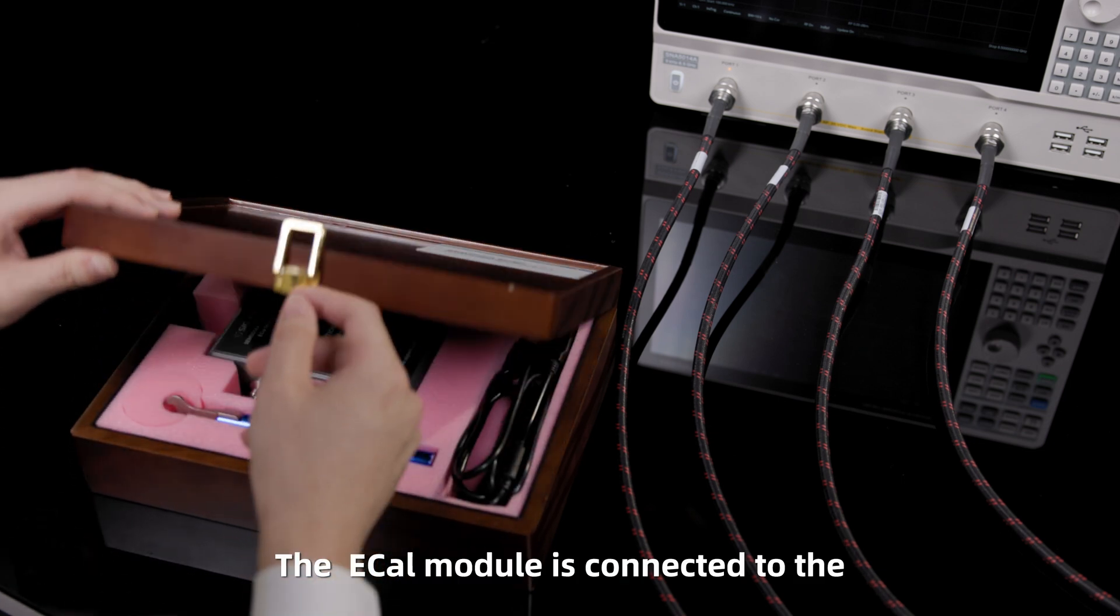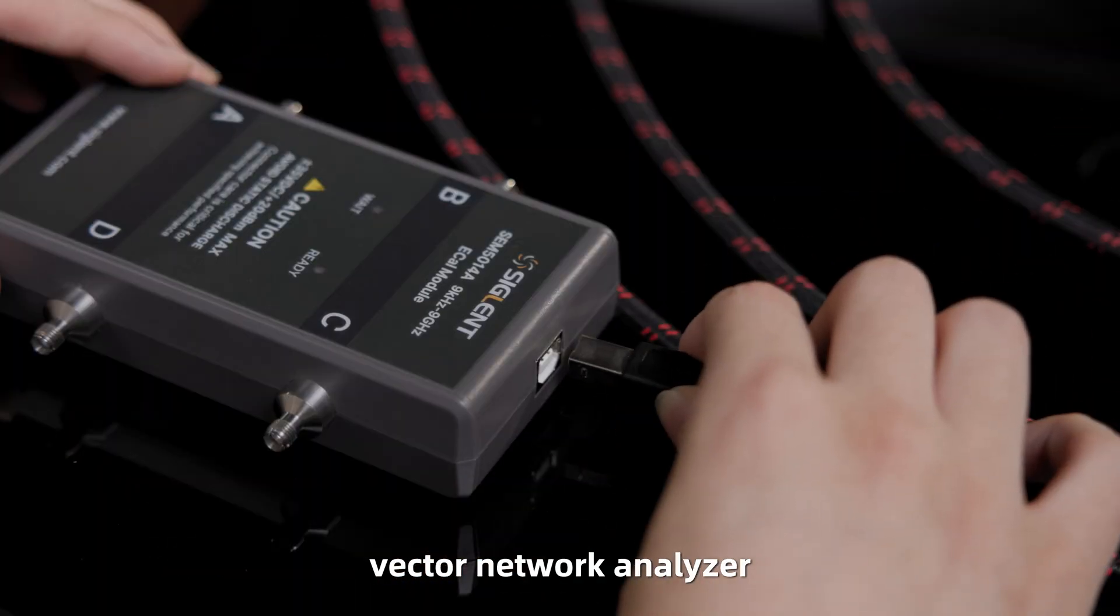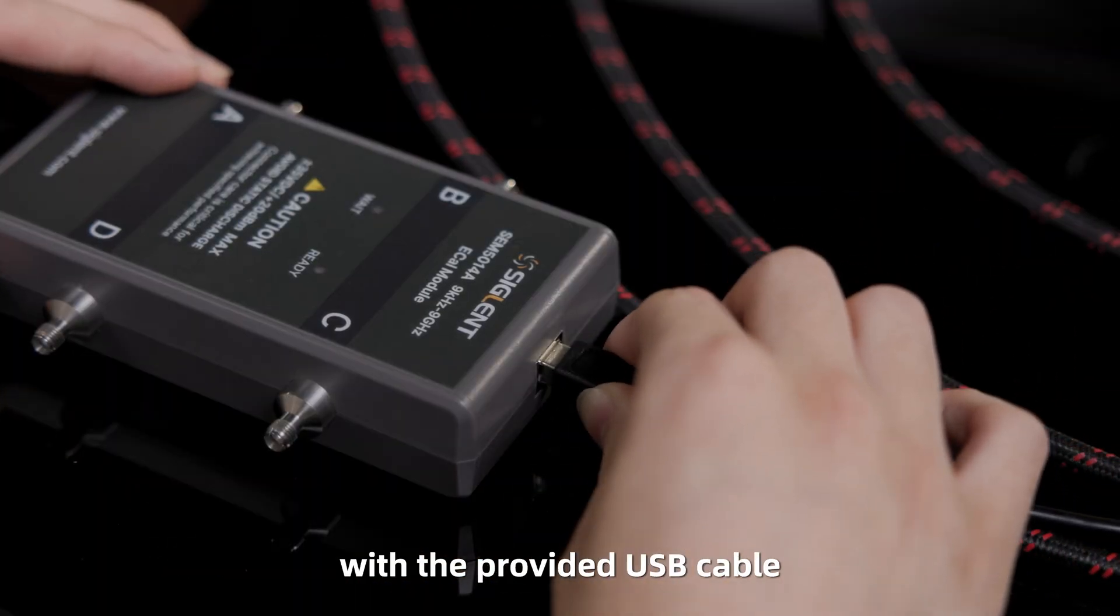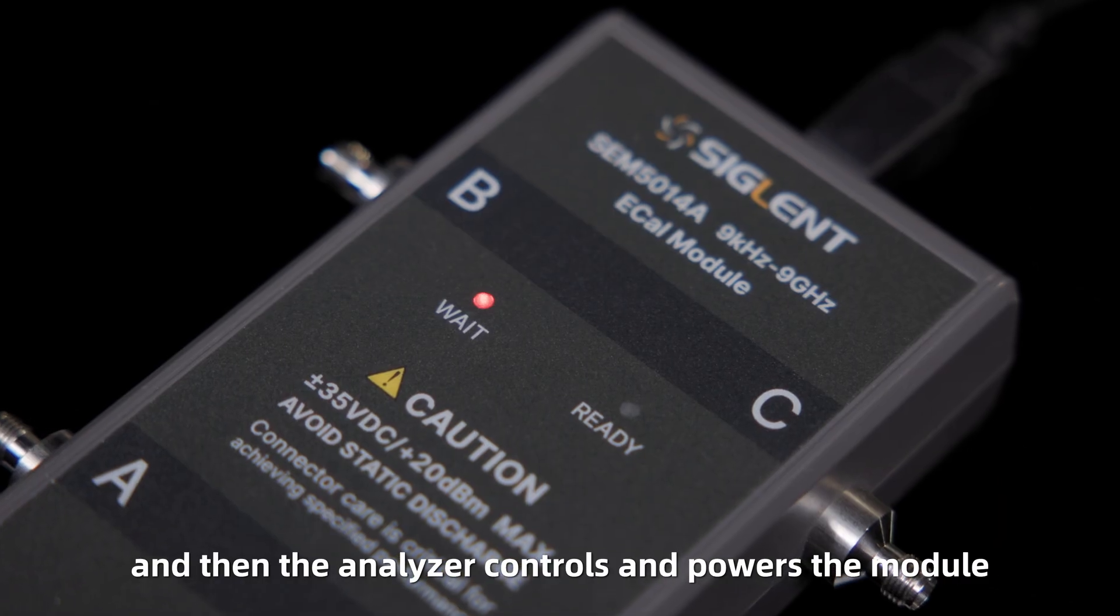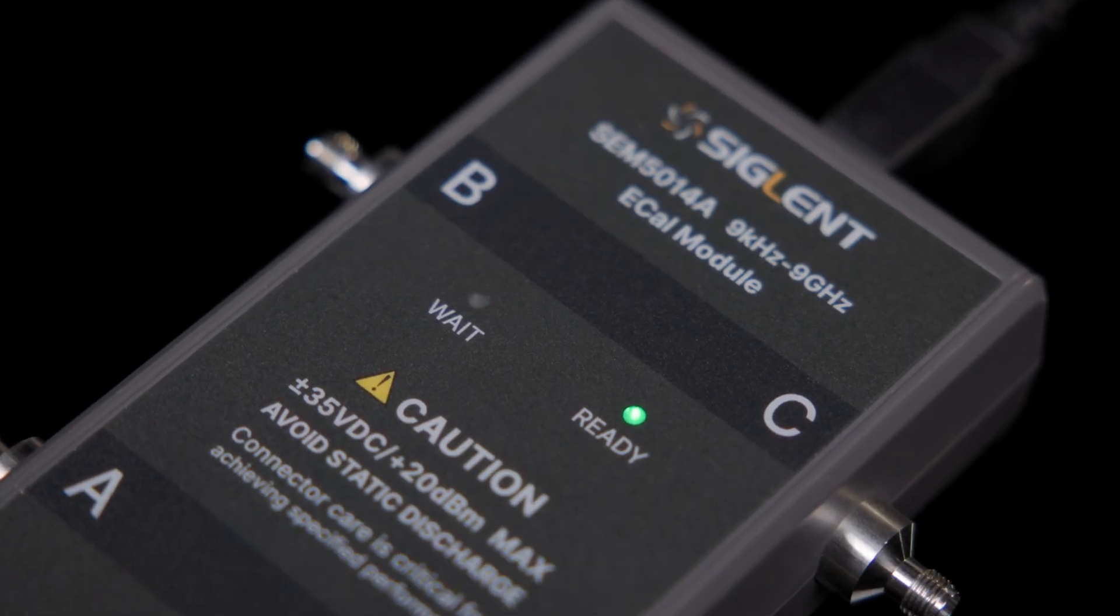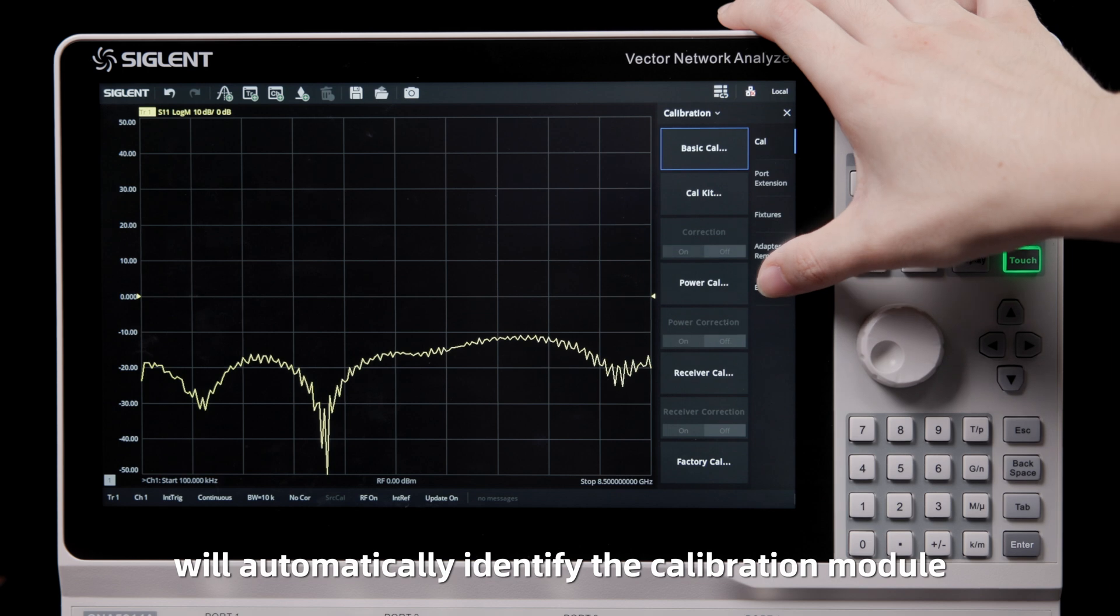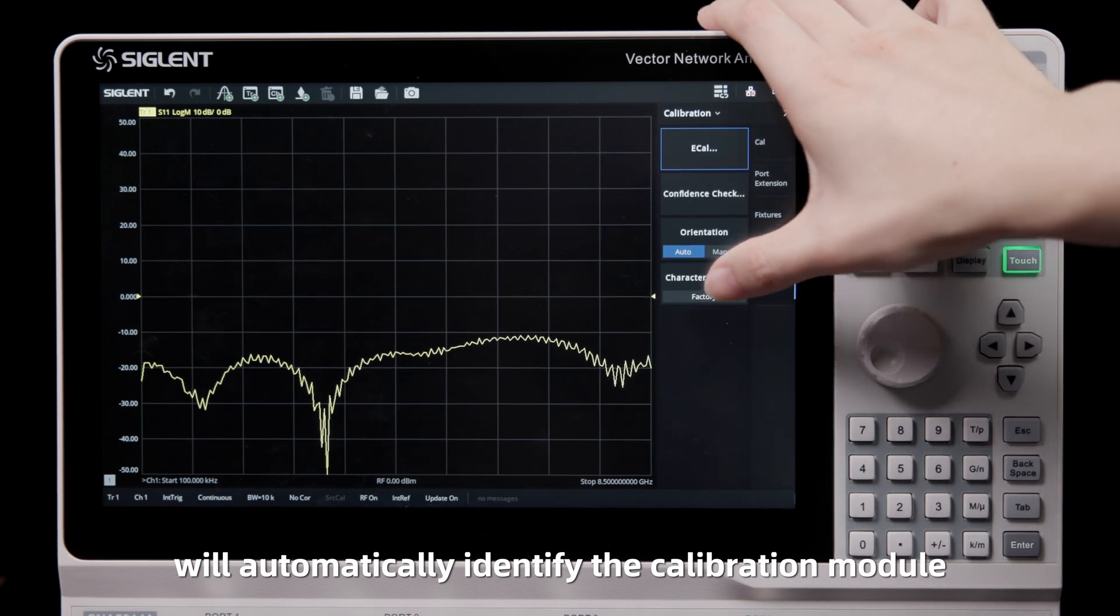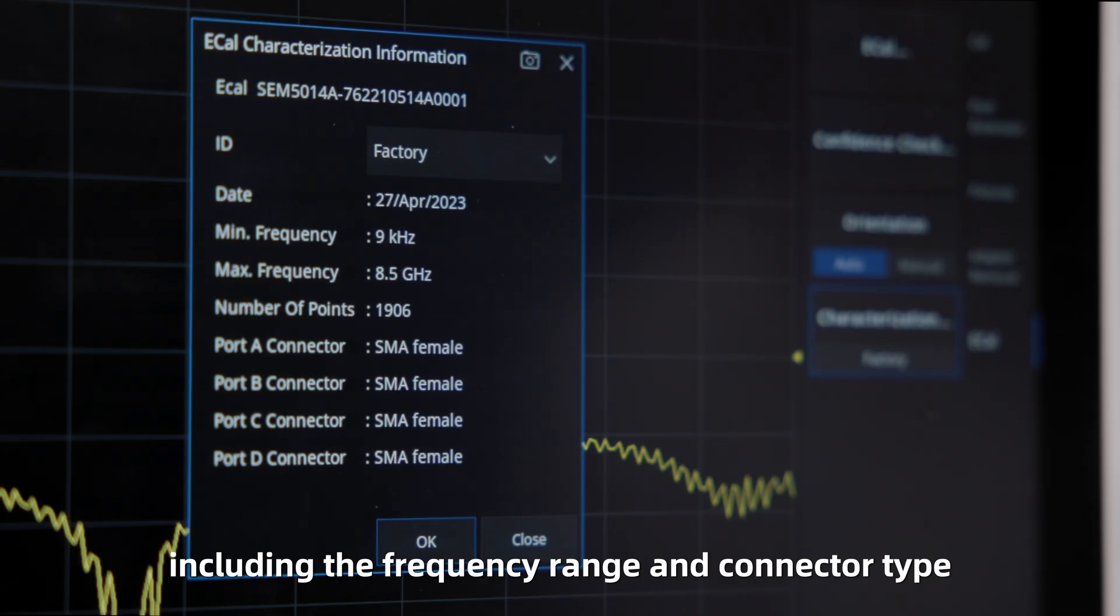First, the ECAL module is connected to the Vector Network Analyzer with the provided USB cable, and then the analyzer controls and powers the module. The analyzer will automatically identify the calibration module, including the frequency range and connector type.